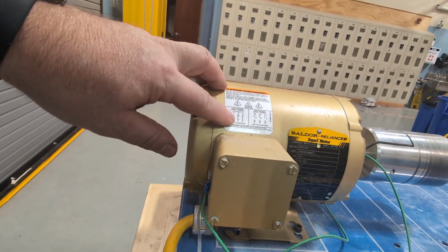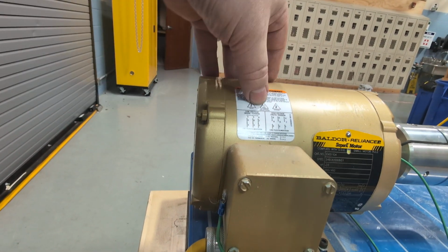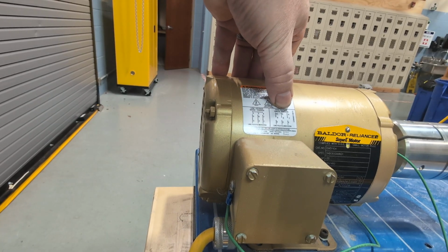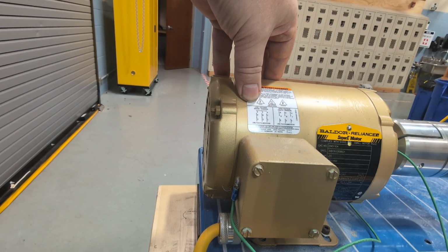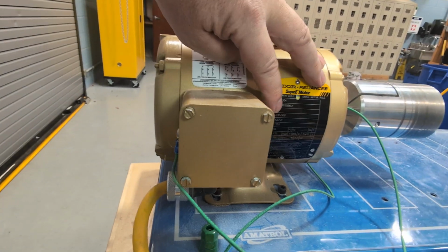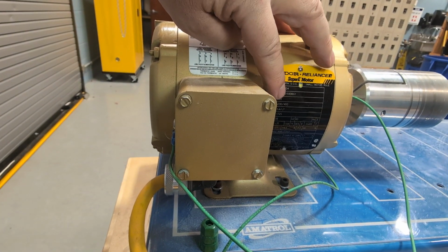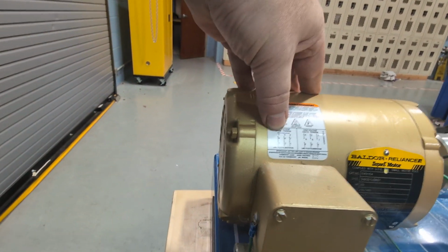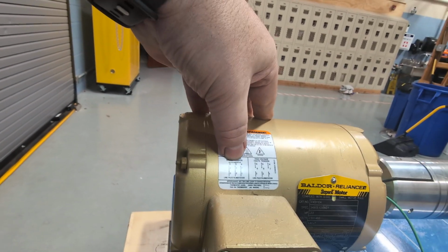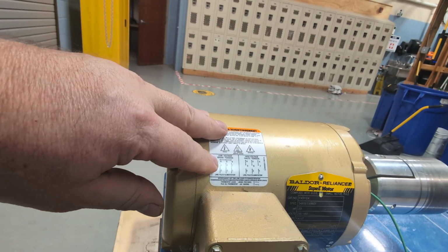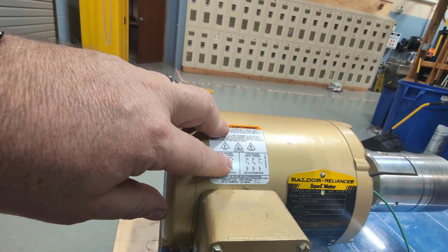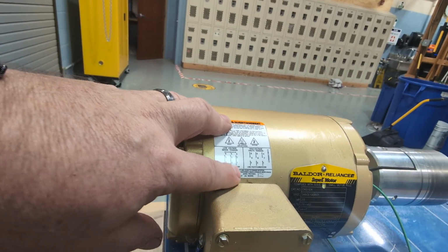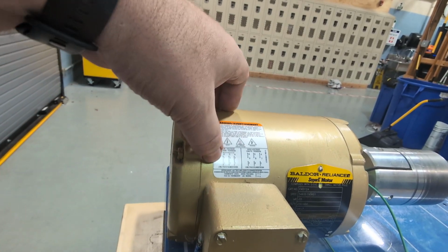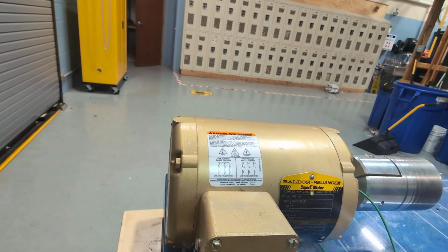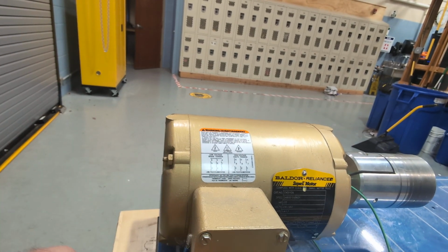Baldor motor. If you look here, this says low voltage. This says high voltage. Low voltage, probably at 230, which you see here. See, it says low voltage and high voltage. Low voltage 230, high voltage 460. Low voltage is showing that points 6, 5, and 4 are connected together. 9 and 3, 8 and 2, 7 and 1 are connected. This is where I put my leads, right here at this spot. 1, 2, 3. My leads get connected here, in here. That's all those wires are in this location.